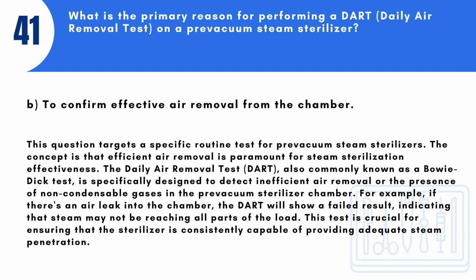Answer: B. To confirm effective air removal from the chamber. This question targets a specific routine test for pre-vacuum steam sterilizers. The concept is that efficient air removal is paramount for steam sterilization effectiveness. The daily air removal test, DART, also commonly known as a Bowie-Dick test, is specifically designed to detect inefficient air removal or the presence of non-condensable gases in the pre-vacuum sterilizer chamber.